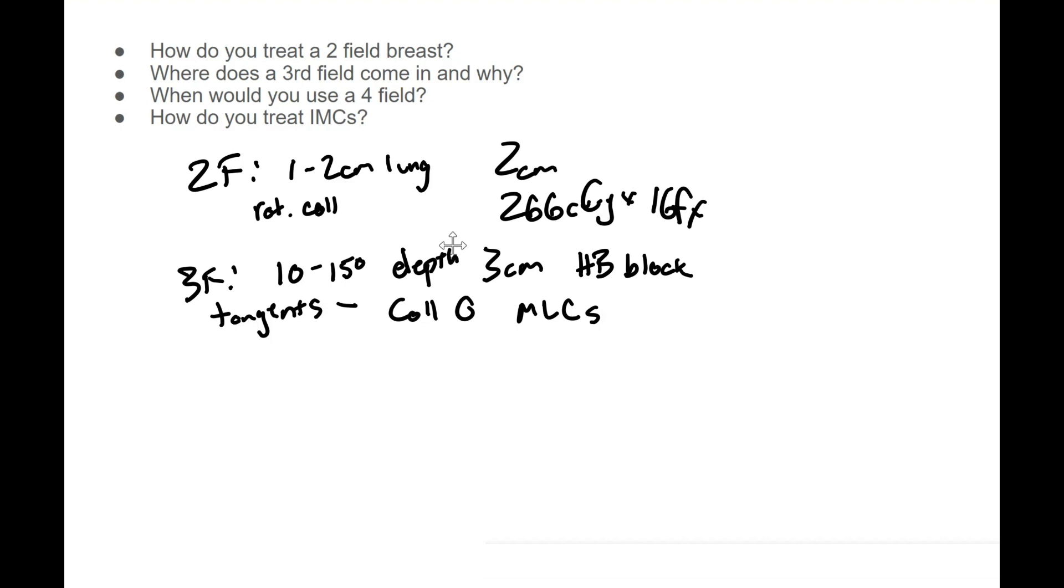So where we have a tangent you kick that collimator and you rotate it to match the actual field size, match the chest wall. Now we aren't doing that - we're using a collimator of zero, you're using the MLCs to block the beam to match the chest wall curvature. You can also if you wanted add a couch kick, and that's going to help match the superior field edge with the match line between the tangents and the supraclavicular field.